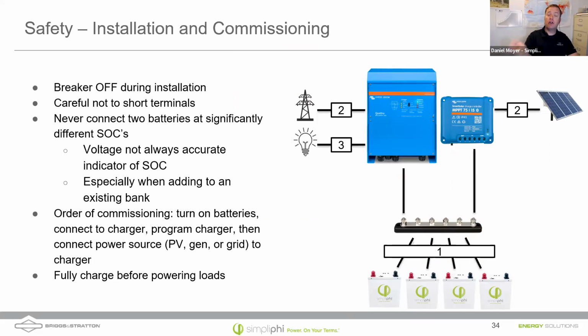Again, Nathan just mentioned you can turn the battery off. How do you turn your car battery off? You don't, right? So there's an internal breaker, which makes it less likely that you're going to short out the terminals. When integrating batteries together, maybe adding new batteries to older ones, make sure you get the batteries at about the same state of charge and follow the right order when connecting them up. You'd have to turn the batteries on to program them correctly, but don't initiate a charge cycle or turn on loads until you get everything dialed in.